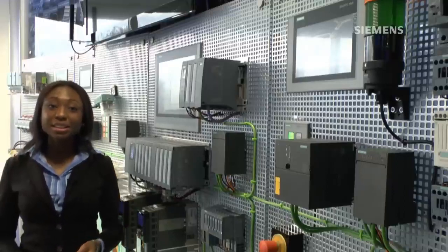Process diagnostics gives you the ability to create your own alarms that are then managed centrally from the SIMATIC controller. PLC alarms are time-stamped by the CPU, giving you millisecond accuracy when diagnosing process faults. You can also embed process values in these alarm messages.